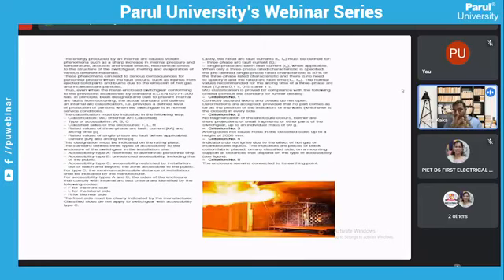Criteria number 1 defines that correctly secured doors and covers do not open. This is relevant when we are sending our switchgears for an internal arc type test and the test results are being approved. All these criteria must be maintained, and there should be no major deformations or major hot gas flowing out of the switchgear. That's how these criteria are described in an IEC standard.